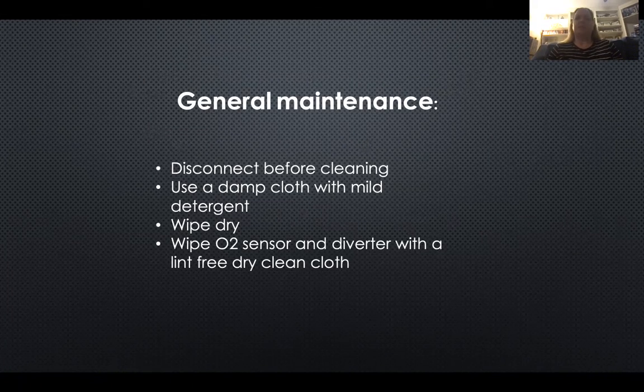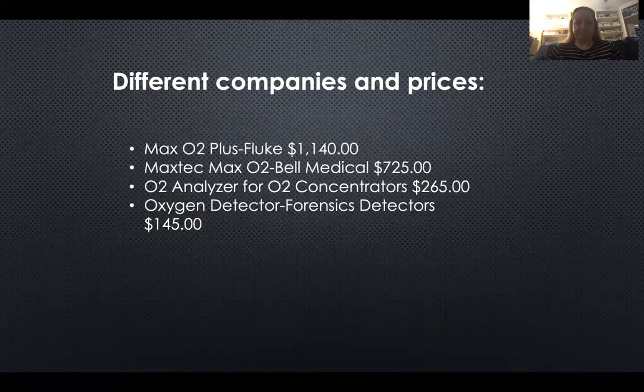Maintenance: make sure it's disconnected before you clean. Use a damp cloth and mild detergent, make sure it's dry, and wipe your O2 sensor and diverter with a dry, clean cloth. Another thing to note is that humidity over 95% can also affect the O2 sensor. So we probably don't want to leave it outside in the middle of summer in Florida.